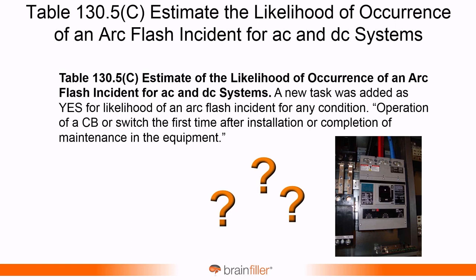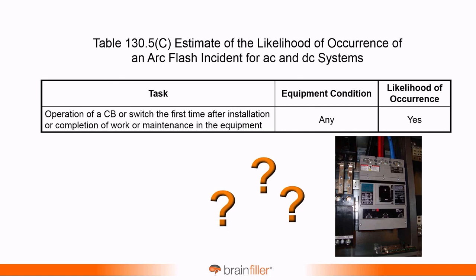And their way of checking a circuit is, oh, we did okay. Let's just throw the switch. If we see smoke, then we know we've got to go fix something. No. You know, is there a huge likelihood when you energize a breaker? Well, I can't contradict this, but within NFPA 70E, the rationale is yes: the first time you're operating a circuit breaker or a switch, after its installation or after completion of work or maintenance, over on the far right, likelihood of occurrence of an arc flash, yes. That is a new change to the 2021 edition of NFPA 70E.